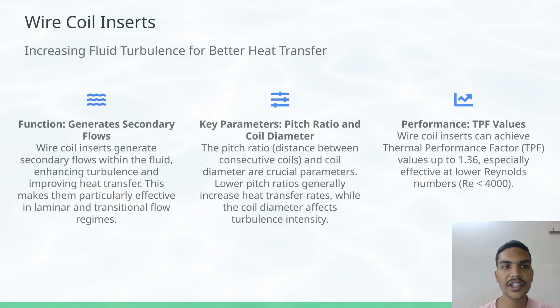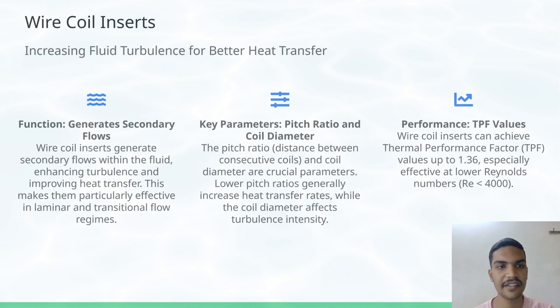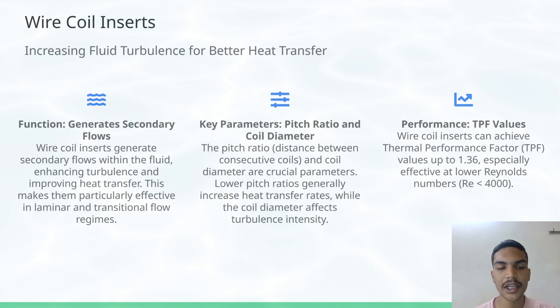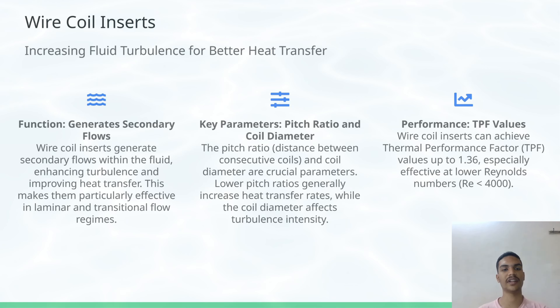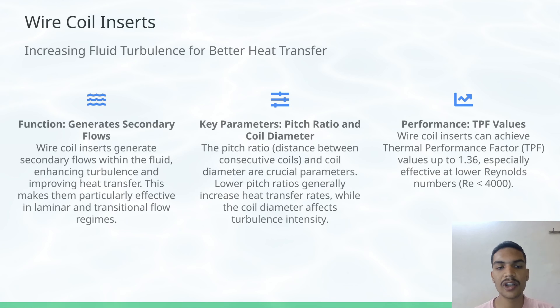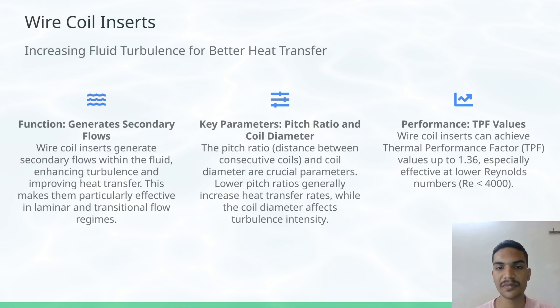The next technique is Wire Coil Inserts. Wire coil inserts generate secondary flows within the fluid, enhancing turbulence and improving heat transfer. This makes them particularly effective in laminar and transitional flow regimes.